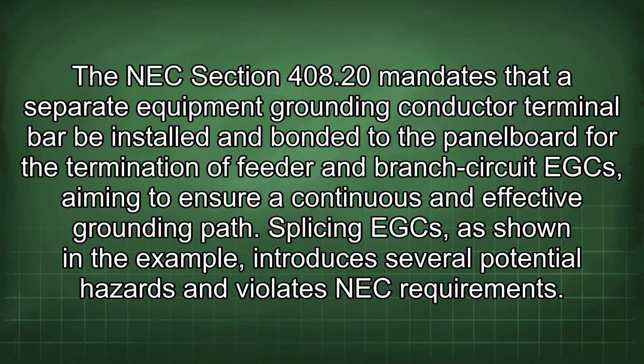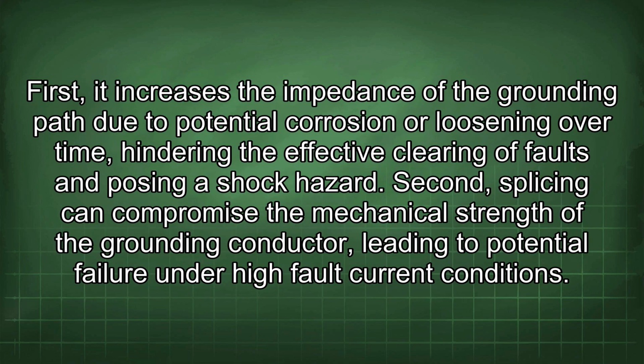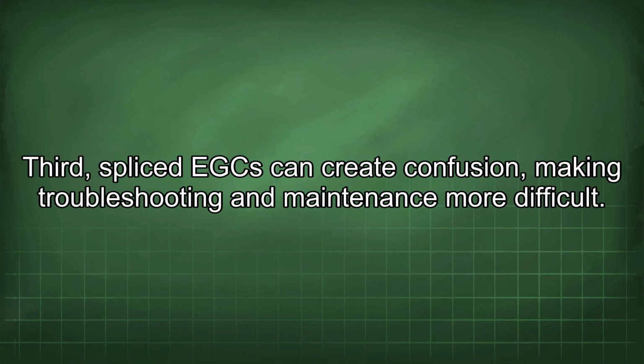Splicing EGC, as shown in the example, introduces several potential hazards and violates NEC requirements. First, it increases the impedance of the grounding path due to potential corrosion or loosening over time, hindering the effective clearing of faults and posing a shock hazard. Second, splicing can compromise the mechanical strength of the grounding conductor, leading to potential failure under high fault current conditions. Third, spliced EGC can create confusion, making troubleshooting and maintenance more difficult.